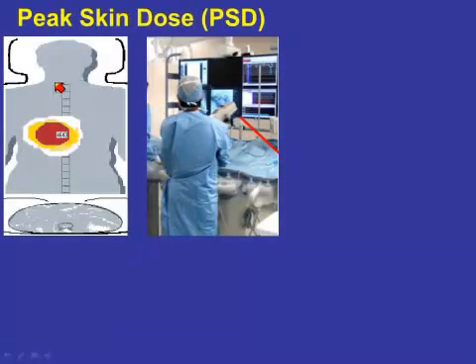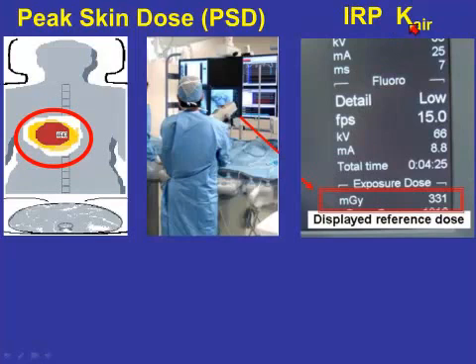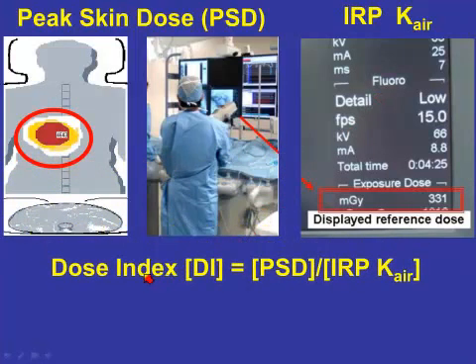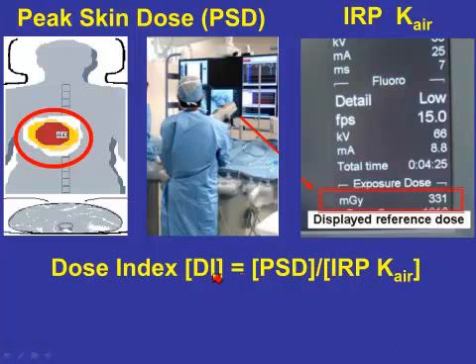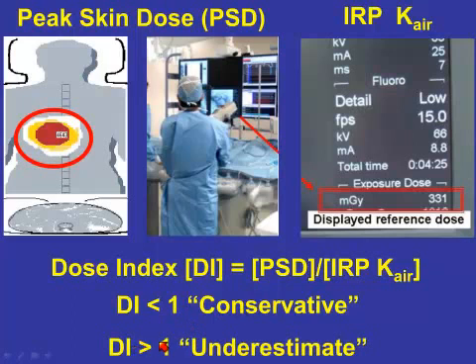Now, if you do a scientific study, you can estimate, calculate, or measure the true peak skin dose. You can also look at the number that your machine is giving you — this IRP kerma rate — and therefore you can quantify a dose index. The dose index is the peak skin dose divided by the IRP air kerma value, both of which are measured in gray. When I teach residents now, I like to say forget formulas — tell me what the formula means. If the number is less than one, you are overestimating the true peak skin dose — you're being conservative. And if the dose index exceeds one, you're underestimating the true peak skin dose. So numbers less than one are good news, more than one are bad news.